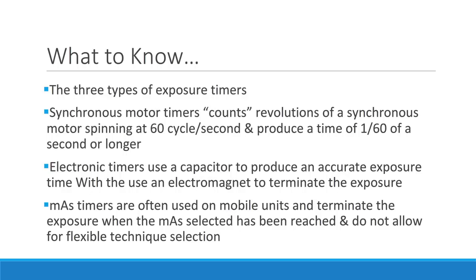When the capacitor is full, it discharges its current, causing an electromagnet to open the exposure switch and terminate the exposure. MAS timers are often utilized on mobile x-ray units — they monitor the total MAS and terminate the exposure when the preset MAS is reached. The MAS is set as a unit and cannot be manipulated into MA and time by the radiographer.